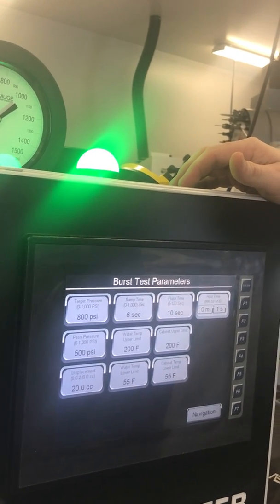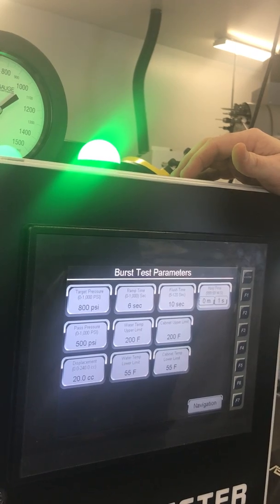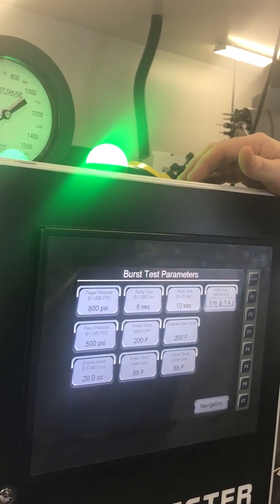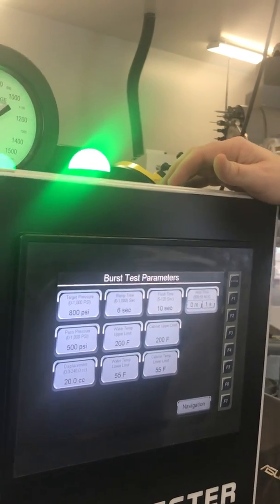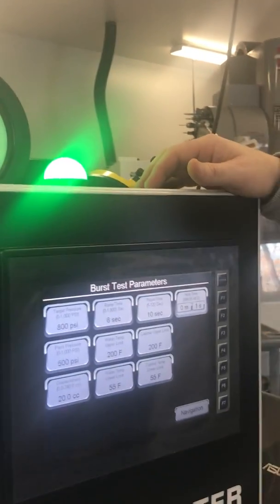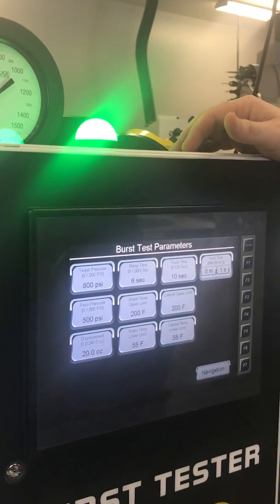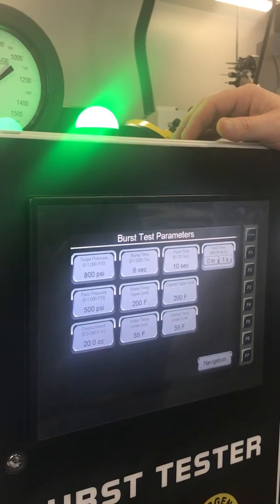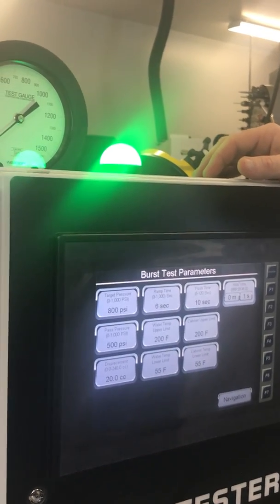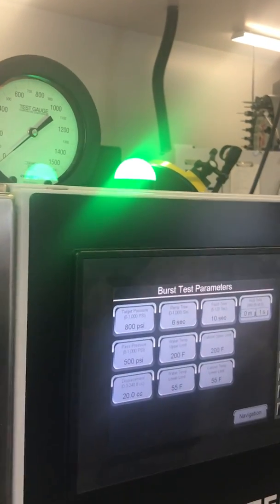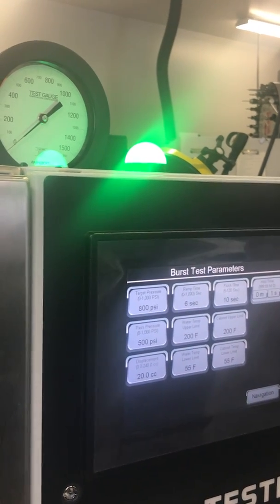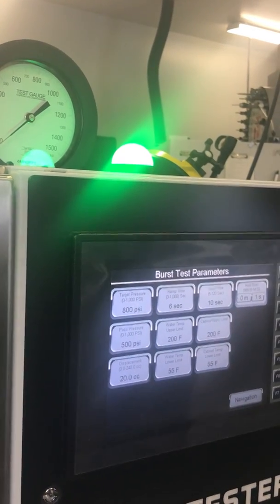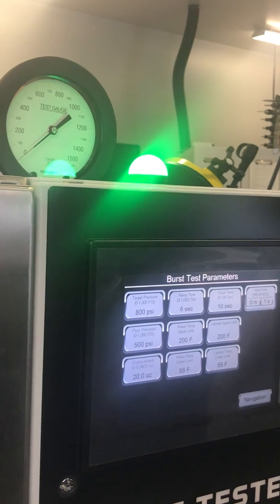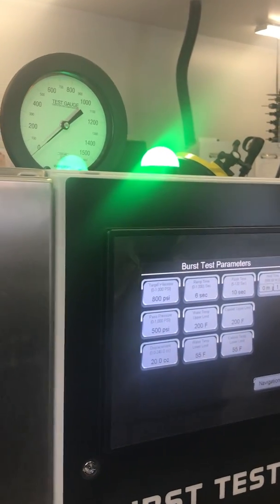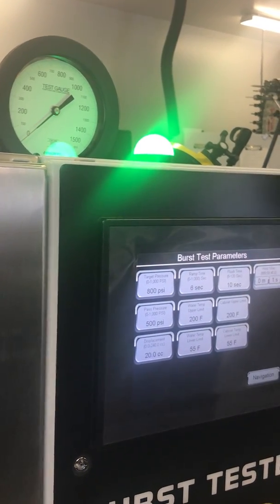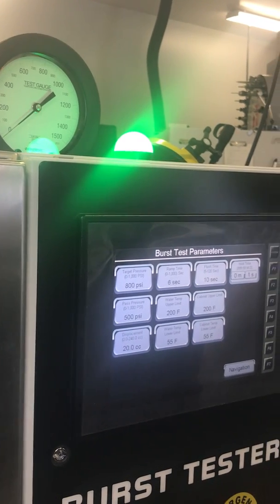Or you can just say, I don't really care, 20, 30, 40, 50, put the number in, and if it leaks, it'll eventually leak to that amount. So what you're doing is telling the machine when to call it. What's my criteria? 20 cc's? You aren't going to know that until you run a few, open the parameters up so it doesn't fail, and see what that displacement is. Then you'll know, here's our target, plus X amount. Right now 20 seems to go pretty good for your parts.